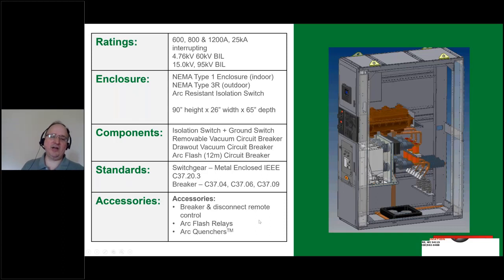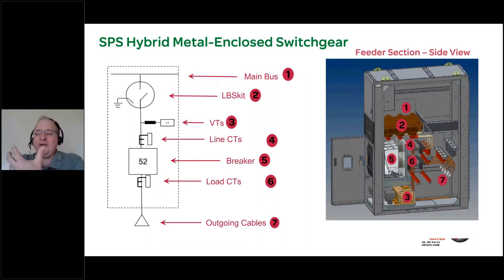It meets IEEE C37.20.3, and with the addition of the optional arc quencher module in this gear, we can create an IEEE C37.20.7 solution, totally arc resistant solution as well. So in terms of what the hybrid switch, when we say hybrid switchgear, the switch is not available fixed mount. So once you include that isolation switch, you can no longer meet the metal clad standard, but you can get most of the functionality. And when I mean most, again, is limited again to that 1200 amp, 25 kA rating.